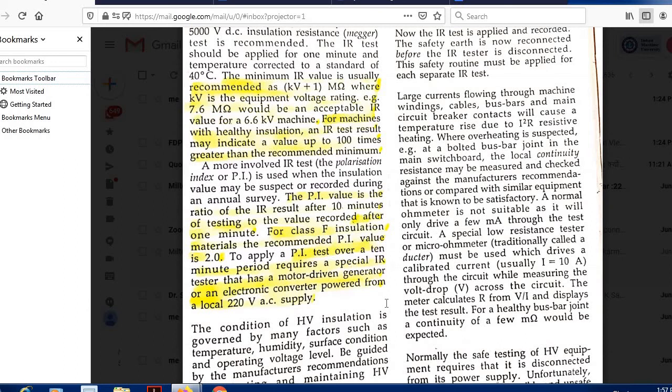Okay, because in positive resistance, RT is equal to R0 (1 plus alpha T). So when you heat the copper conductor, its resistance increases. That we find by RT is equal to R0 (1 plus alpha T). But in case of high voltage, in case of insulation, the insulation has got a negative temperature coefficient characteristic. So when you heat it, the insulation resistance will decrease.